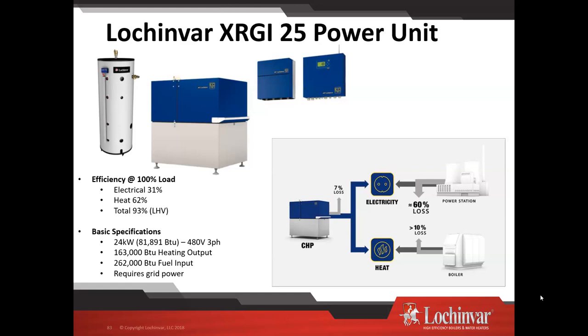What we have here is you've got this blue and gray box. What it is, it's essentially a Toyota forklift engine. We've got a liquid cooled jacket in this blue portion. We've got heat exchangers and pumps in this unit, and then we have all electrical in here. Simplified the most, it's a generator that we're taking the heat off of, producing electricity for the building, and then dumping the heat into domestic and space heating.